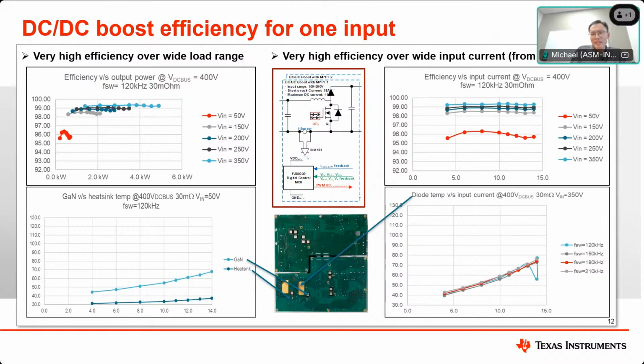It can be seen that the converter operates well with input voltages as low as 50 volts, with the limitation that the input current was limited to 14 amps. We see the output power is of course only 700 watts. It can be seen that the efficiency is already in the range of 96%. With increased input voltage from 150 volts up to 350 volts, the achieved output power increases gradually to 4.9 kW for one PV input. The efficiency is at a really remarkable 99%, clearly showing the benefits of GaN.